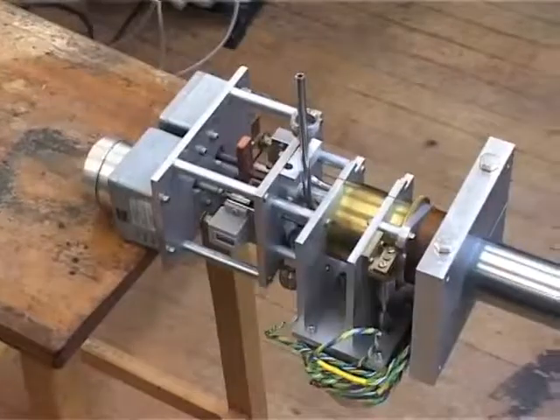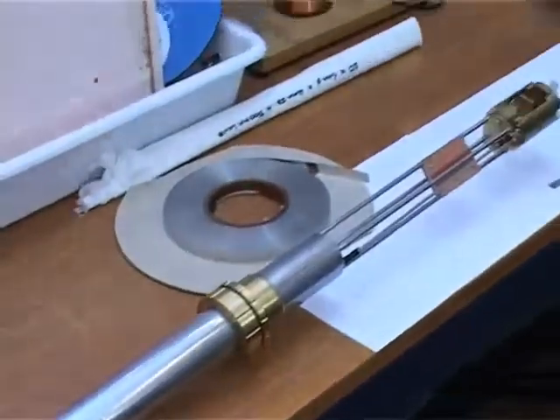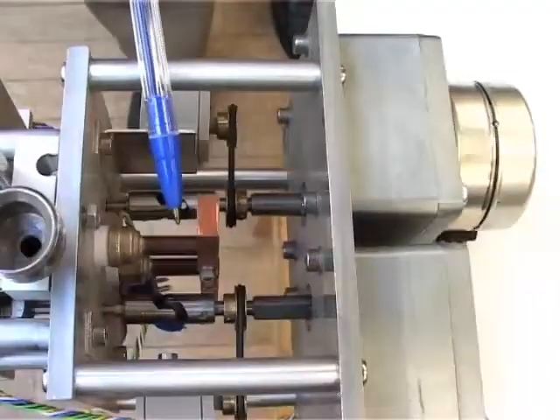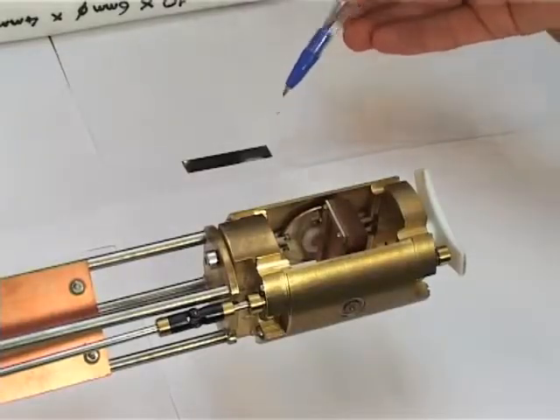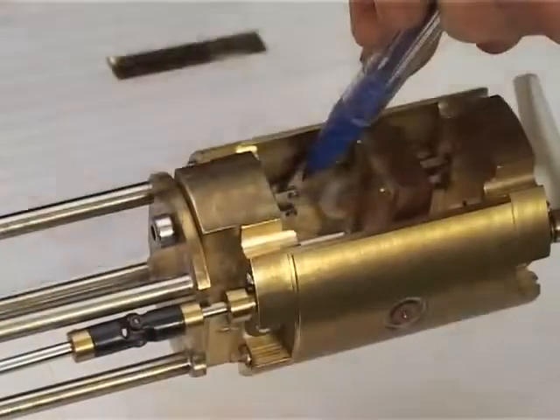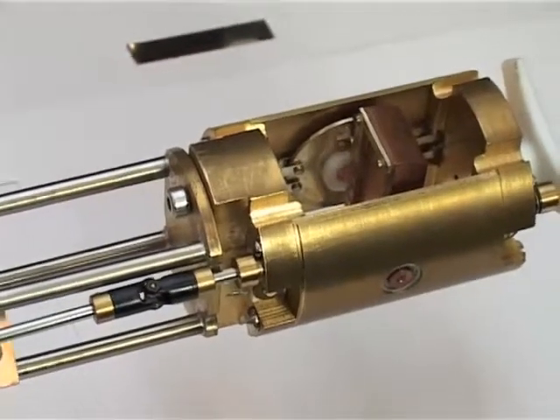Most goniometers will only support low current measurements for thin bridges of superconducting material. To measure a full width of a coated conductor, we need higher transport currents. This goniometer will support currents up to 300 amps. A large current can be applied to these copper blocks here. A sample like this can be mounted on the copper block here, and current applied using sliding contacts here. The entire block can be rotated under the control of stepper motors.